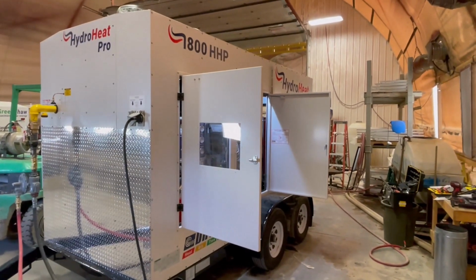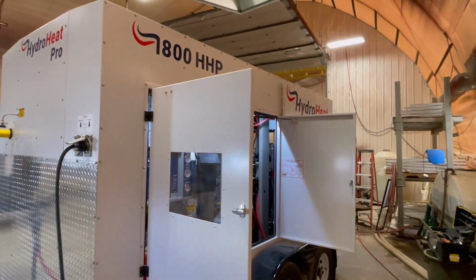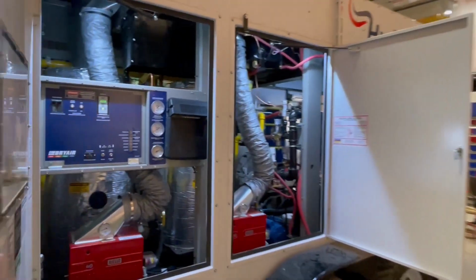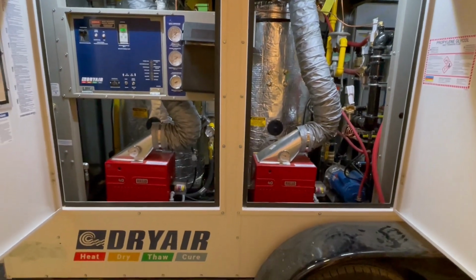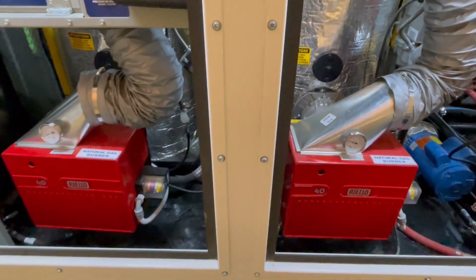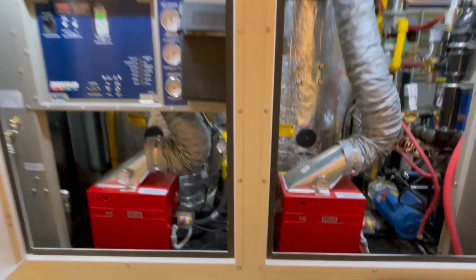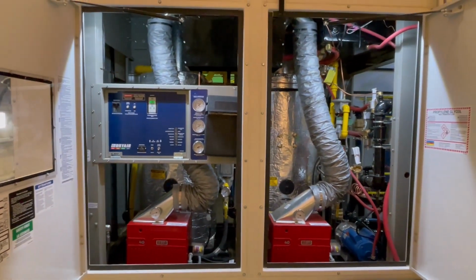This is the DryAir 1.8 million BTU Hydro Heat Pro. It is a dual burner system. This one currently has natural gas burners installed. These burners are a single stage burner and will both fire and shut off at the same time as the temperature controller calls for heat.